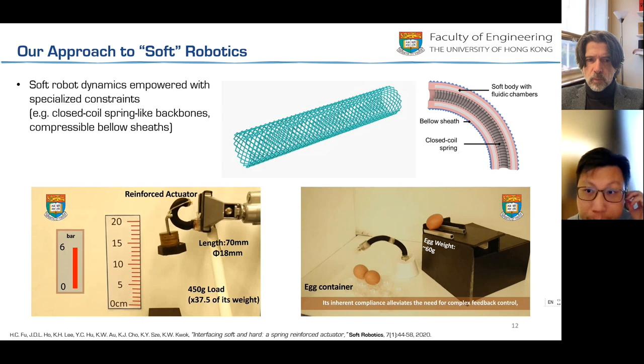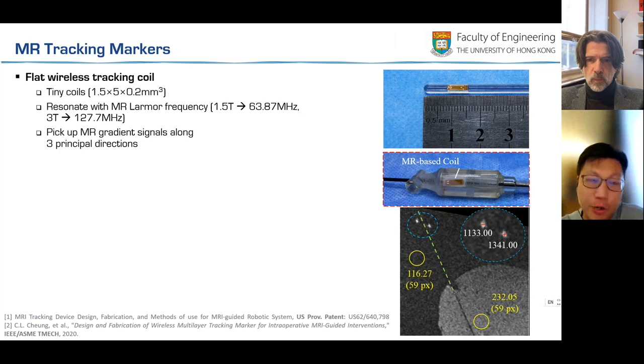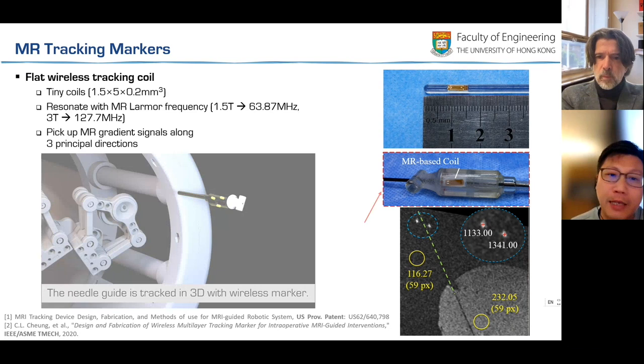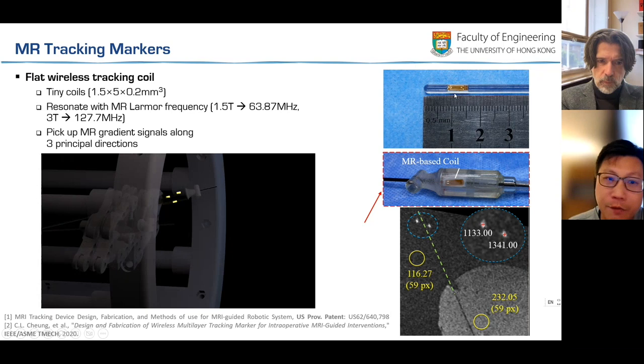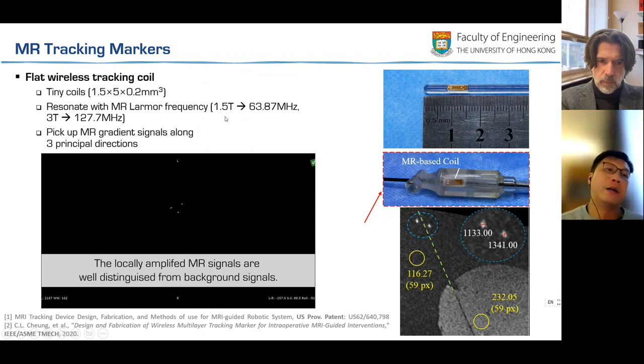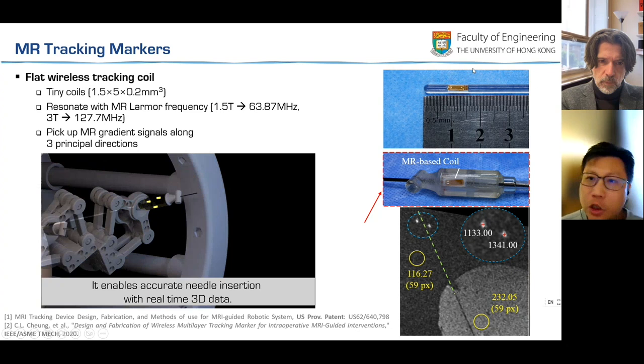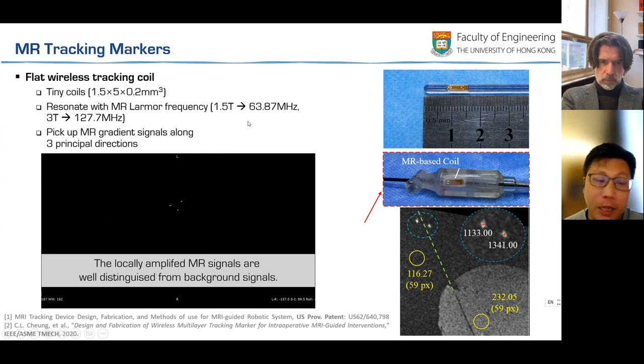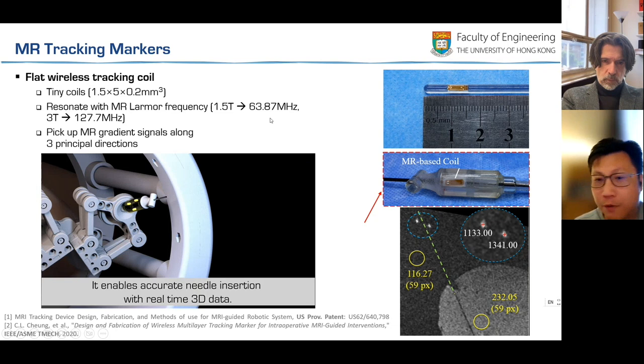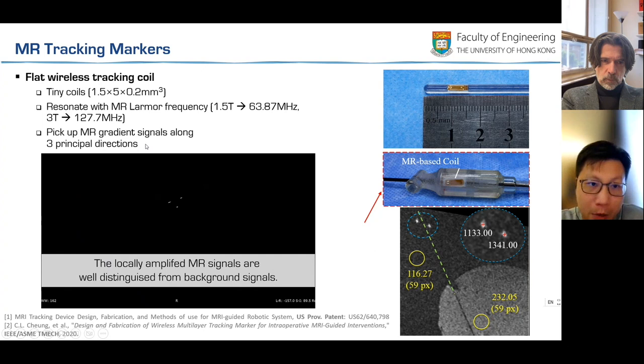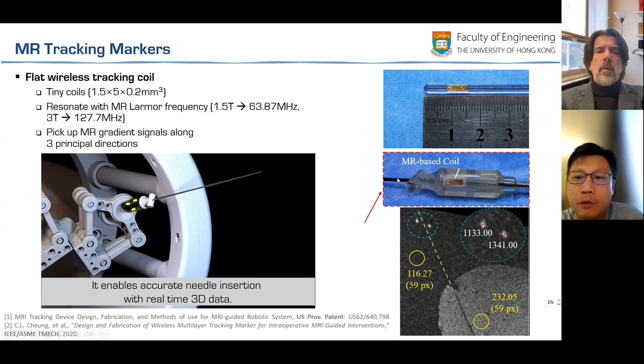Apart from the actuation, it's time to introduce the tracking marker, the sensor. This is a sensor we fabricated in our laboratory, particularly for the 1.5 Tesla MRI machine. This circuit is actually a resonant circuit that can resonate at the Larmor frequency of 1.5T, which is 63.87 megahertz. We can pick up very high MRI gradient signals along the three principal directions, and even update the tracking position very fast.